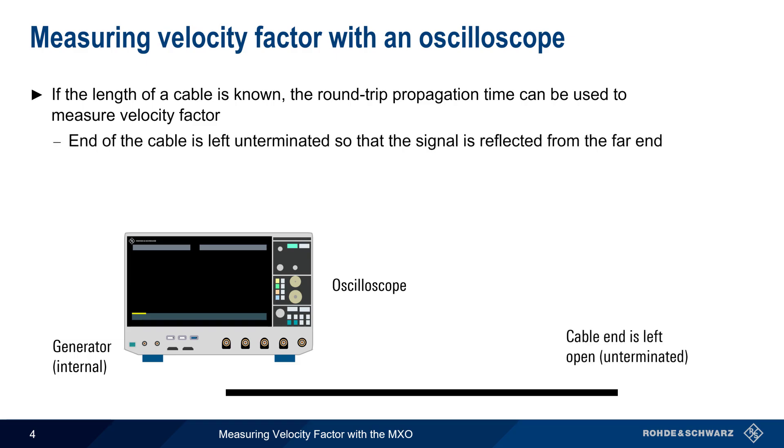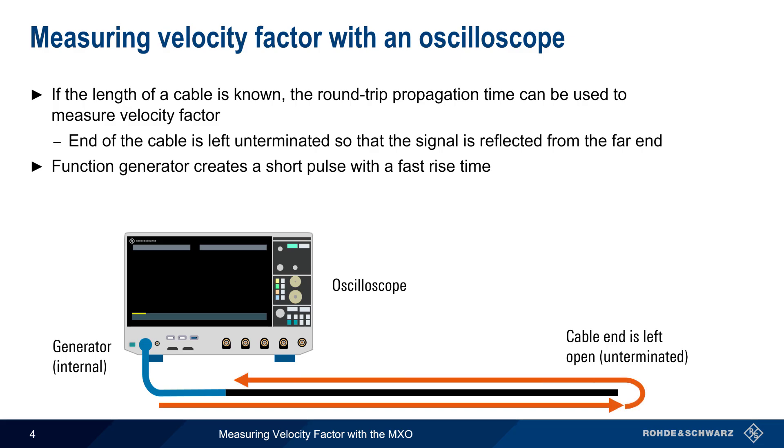The end of the cable is left unterminated, so that our stimulus signal will be reflected by the far end. We use the function generator to generate a short pulse with a very fast rise time, and an oscilloscope channel is configured to capture both the transmitted pulse and the reflected pulse. The time difference between them is then measured and used to calculate velocity factor.